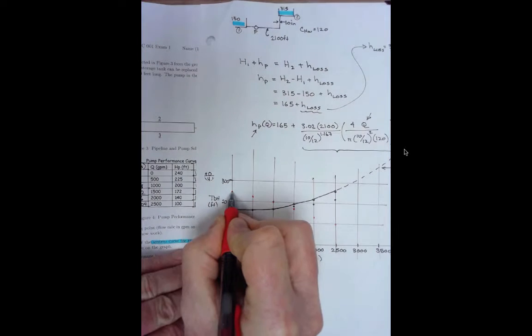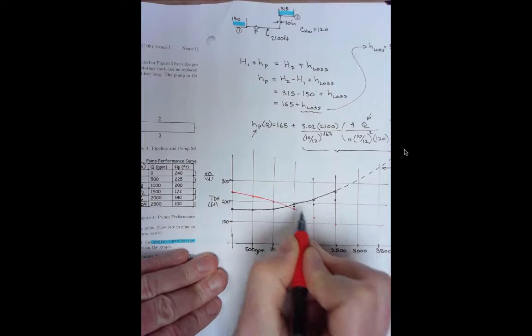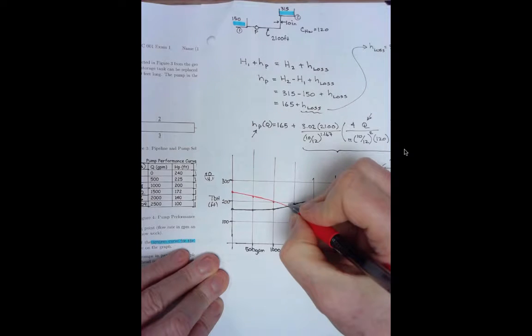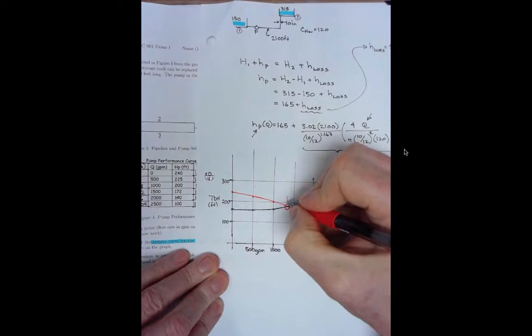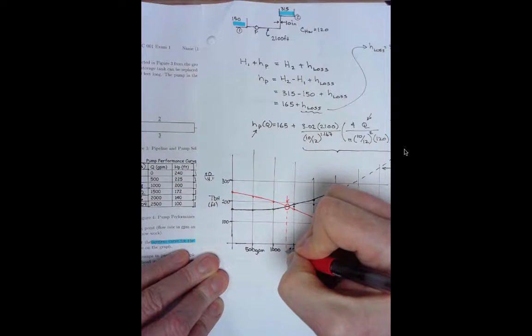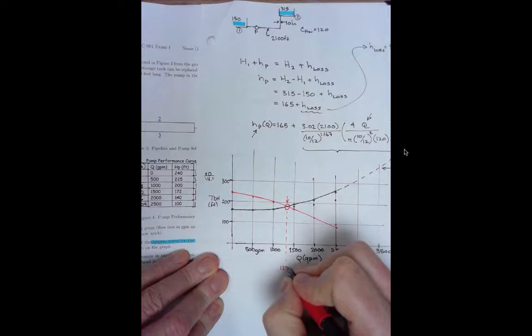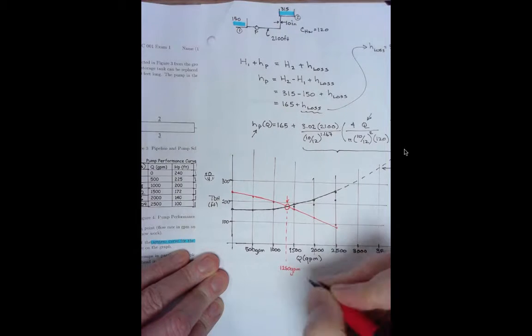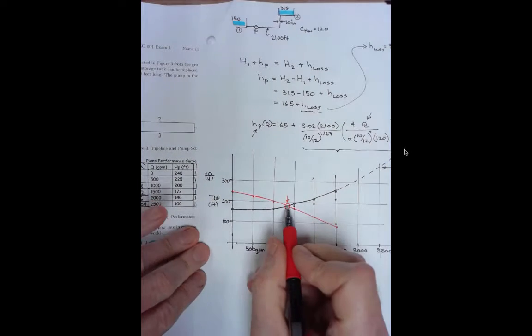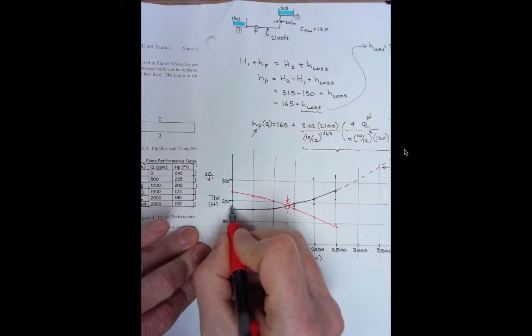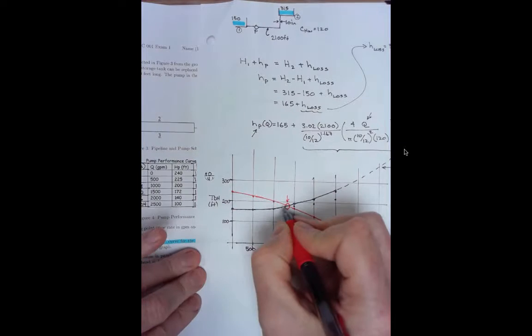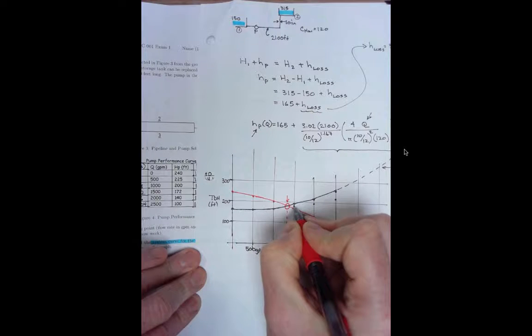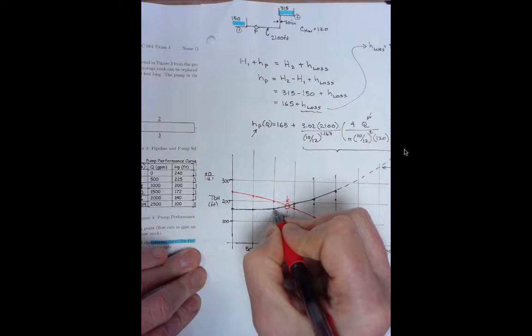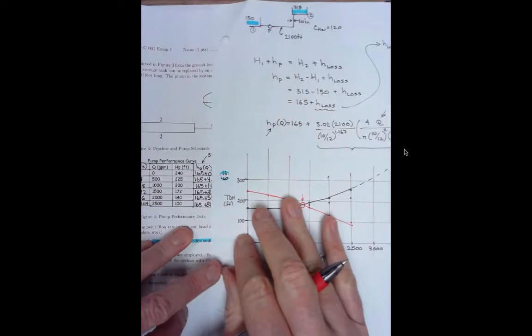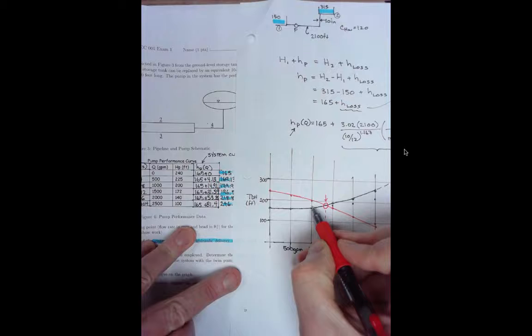Our operating point is right about there. And I'm lazy, so I'm going to declare that 1,250 gallons per minute. And my total head is probably about 180. Let's see what I'm at. That's it. 180. 165, 169. Yeah, about 180.